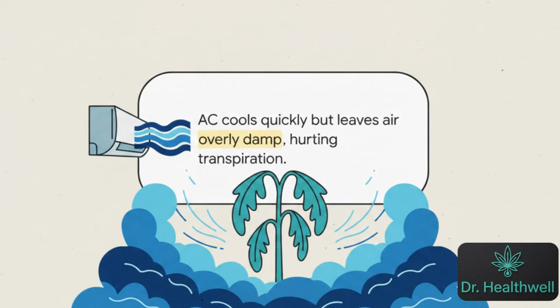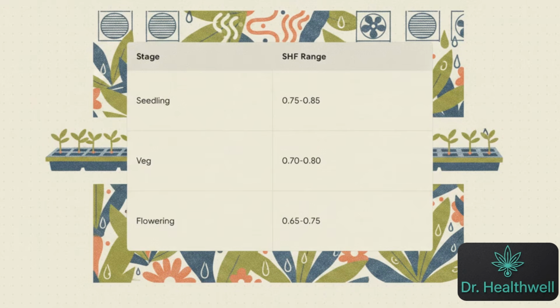These high-ratio air conditioners rapidly hit their temperature set points and shut off before extracting substantial moisture, creating a dangerous vapor lock that leaves the environment cold, damp, and highly stressful to the canopy because the plants simply cannot transpire properly. An ideal greenhouse HVAC system actually requires a carefully tuned sensible heat factor, typically between 0.65 and 0.85 depending on the exact growth stage, to properly balance sensible cooling with heavy, continuous dehumidification throughout the crop cycle.